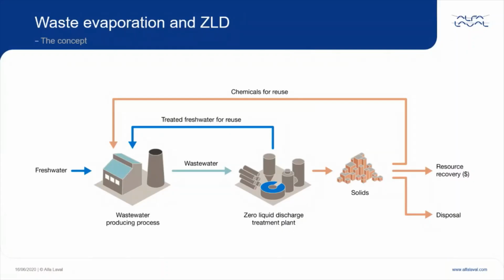The starting point is that most industrial processes will use fresh water at some point, which will often result in a wastewater stream. And this is where the zero liquid discharge system comes in to treat this wastewater. The ZLD system uses a combination of technologies and process steps involving heating, separation, decanting, and evaporation to separate the wastewater into two end products: the treated water, which is clean enough to be reused, reducing the consumption of fresh water, and the solids fraction, which can either be recycled back to the process, sold as a product, or disposed of, depending on what type of solid it is and its quality.